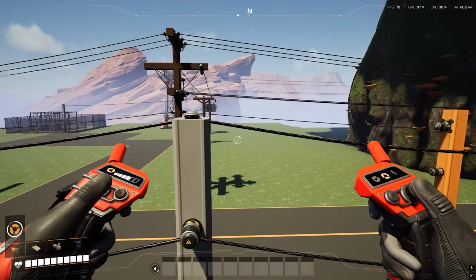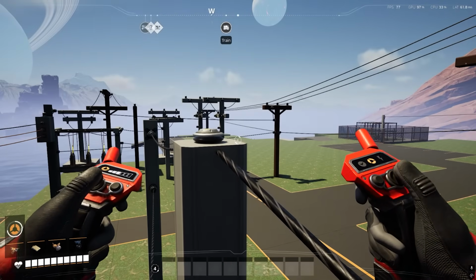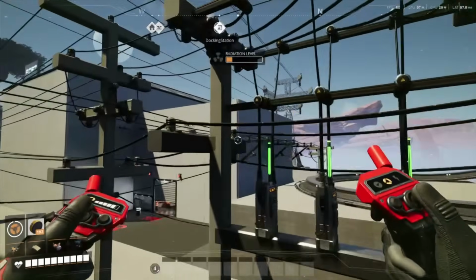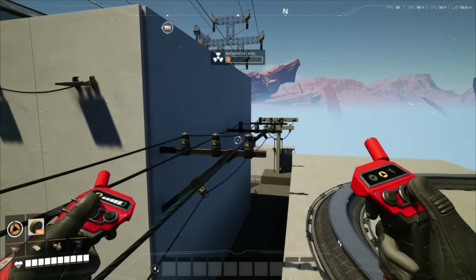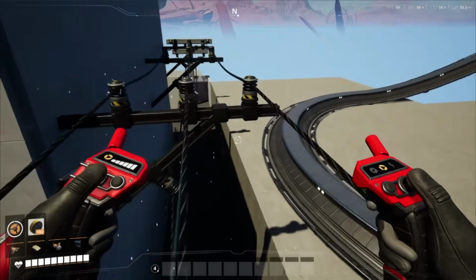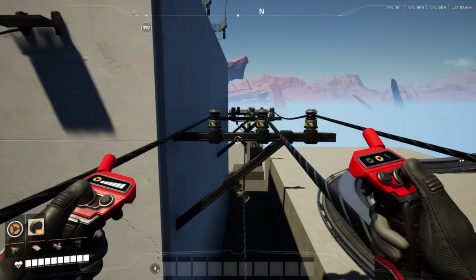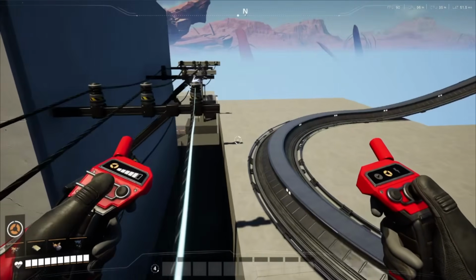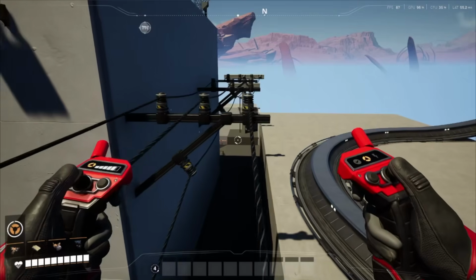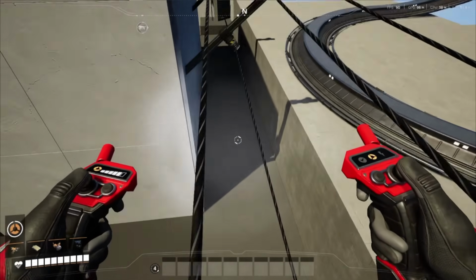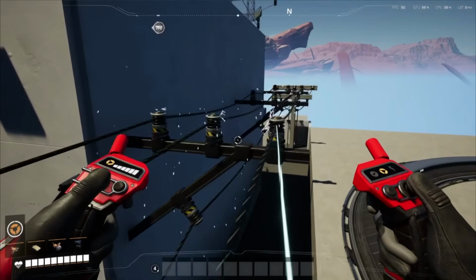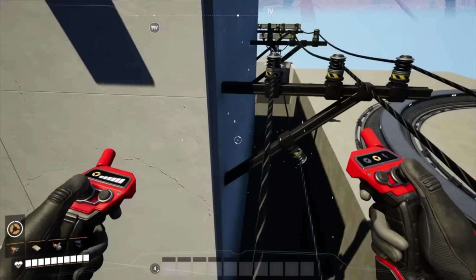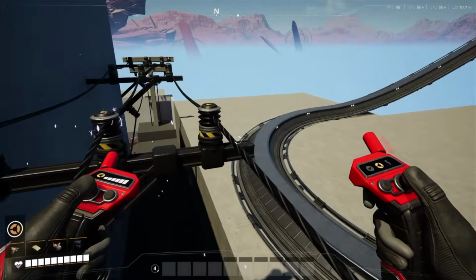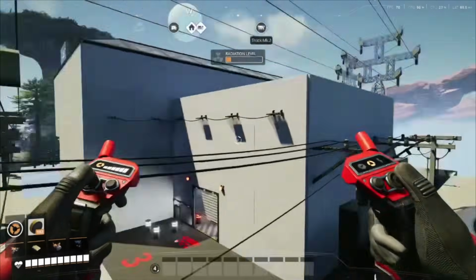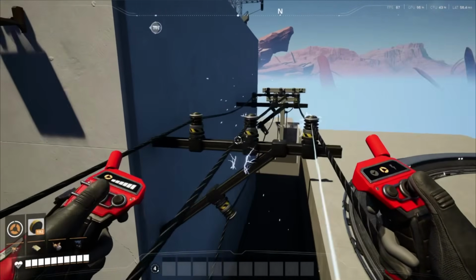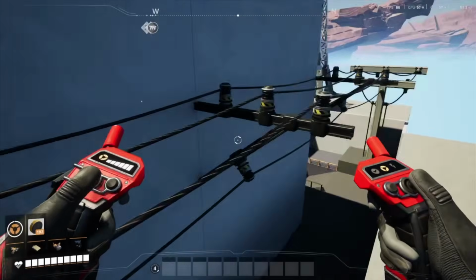You're going to make sure you've got a fair separation between your neutral and your primary insulator. In situations like this, where you have low line clearance, meaning you couldn't really fit a pole in here without it looking awkward, or in real life this would not give us the clearance to build a pole. But in the instance you have to build something back here and you don't have clearance for a pole for reasons like this, you can do alley arm construction. The pole would come up here and your arm would come out from the pole. Instead of being even on the pole, it comes off to one direction. This allows you to maintain line clearance in tight spaces.